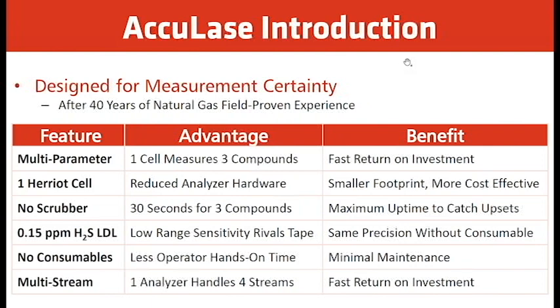The low range sensitivity is the best on the market from an LDL point of view for lasers, which is 0.15 ppm for H2S. And it has the ability to be multi-stream, so we can do up to 4 streams in a single analyzer. So all of these things really equate to lower maintenance and higher reliability.